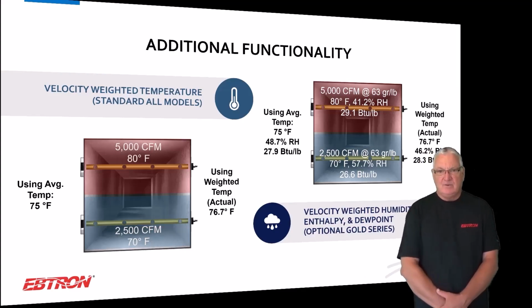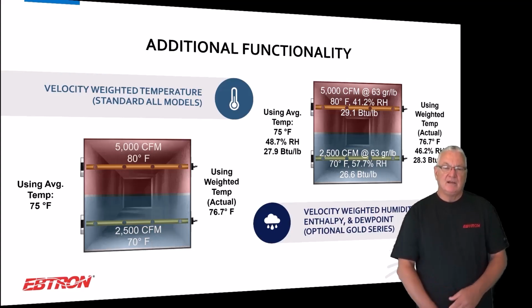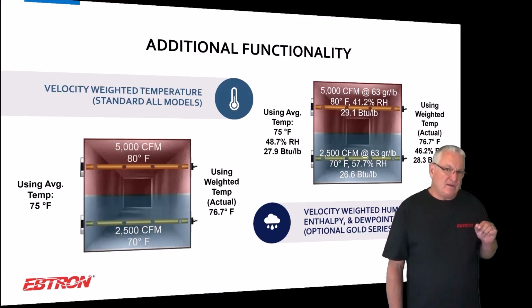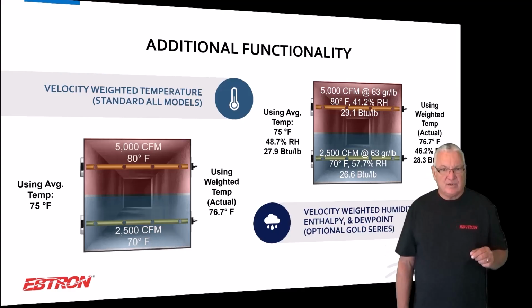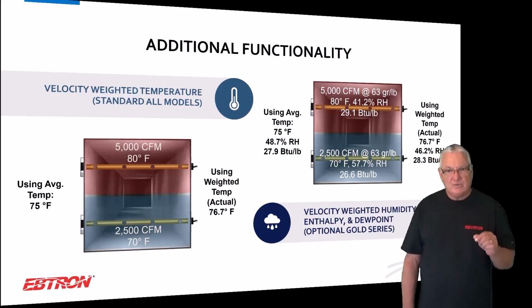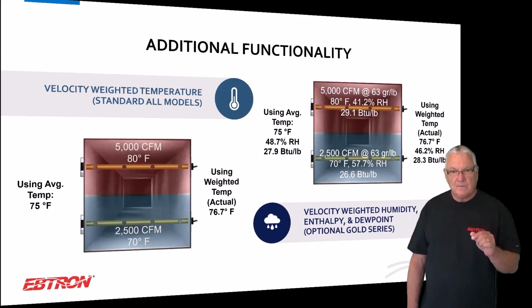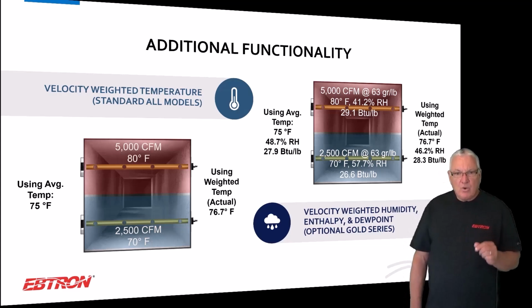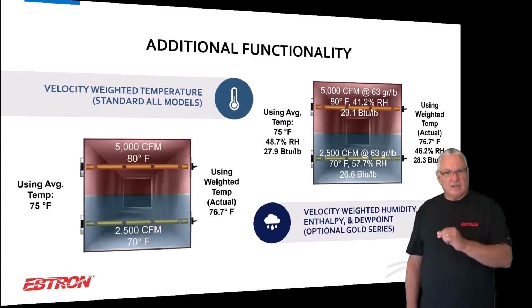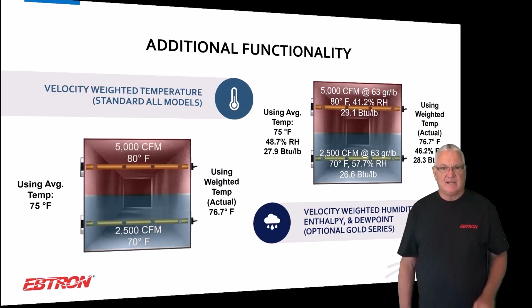Okay, so velocity weighted temperature, you find that the actual enthalpy of that airstream is 28.3 BTUs per pound. And that's it for economizer switchover. I see people that are measuring in the wrong place. What you want to know is what is the enthalpy of the air entering the mixed air plenum, not on the roof. What is the air mixing with the return air? And it's what's coming through your outside air intake.